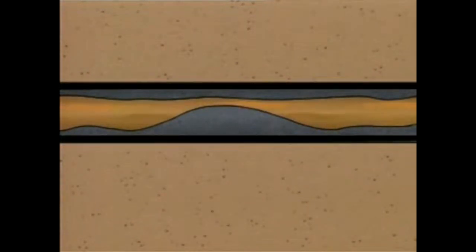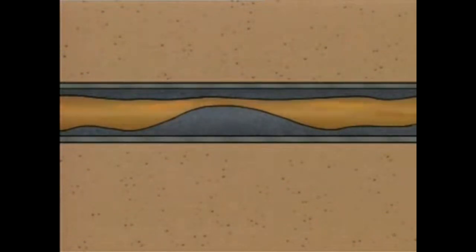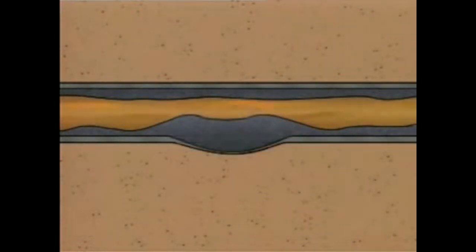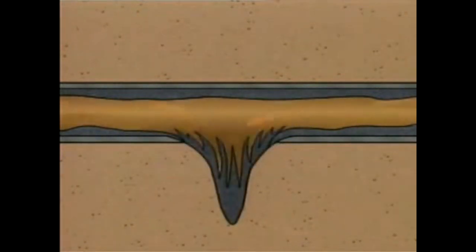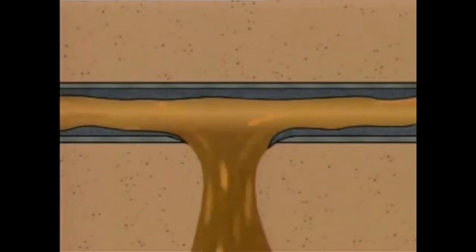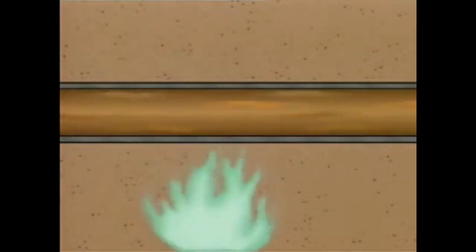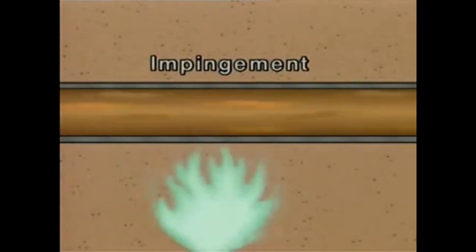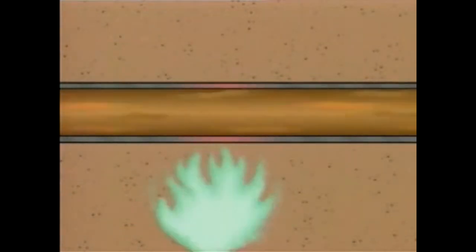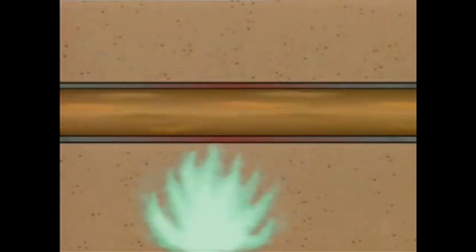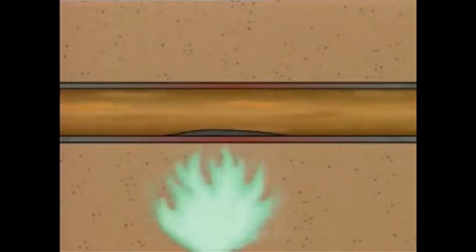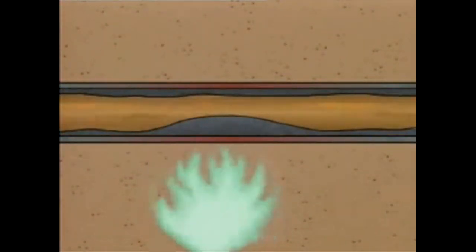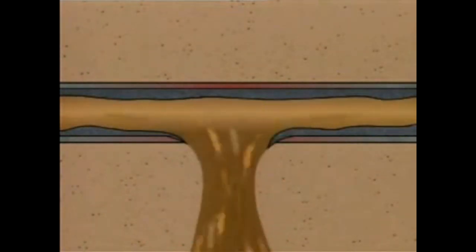Carbon deposits insulate tube walls, which reduces the amount of heat that is carried away from the tube by the process fluid. If this situation is not corrected, the tube could overheat, weaken, and eventually rupture. Coking can also develop if the burner flames come into contact with the tubes. This problem is called impingement. Impingement can create hot spots on the tubes that can lead to the formation of carbon deposits. If the impingement problem is not corrected, the tubes could eventually rupture.